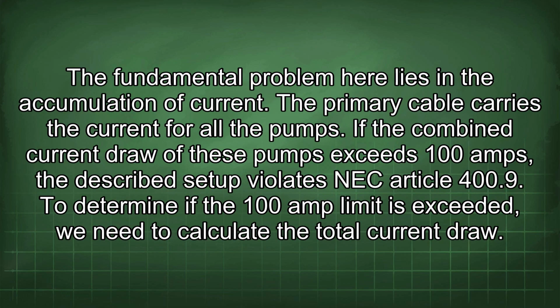The fundamental problem here lies in the accumulation of current. The primary cable carries the current for all the pumps. If the combined current draw of these pumps exceeds 100 amps, the described setup violates NEC Article 400.9. To determine if the 100 amp limit is exceeded, we need to calculate the total current draw.